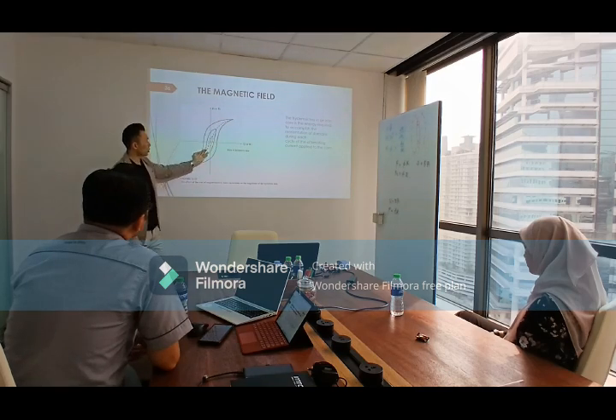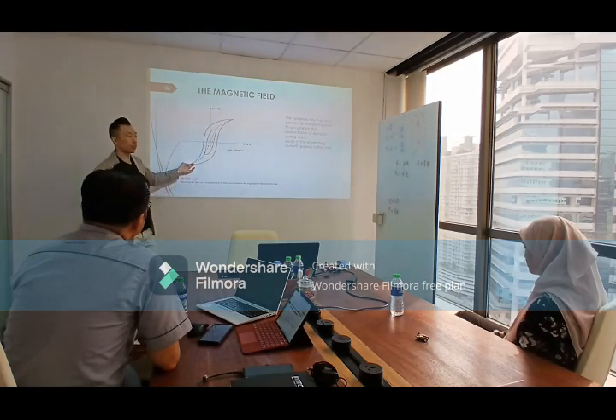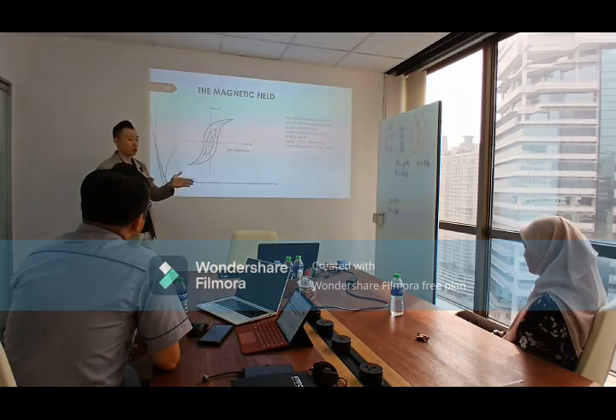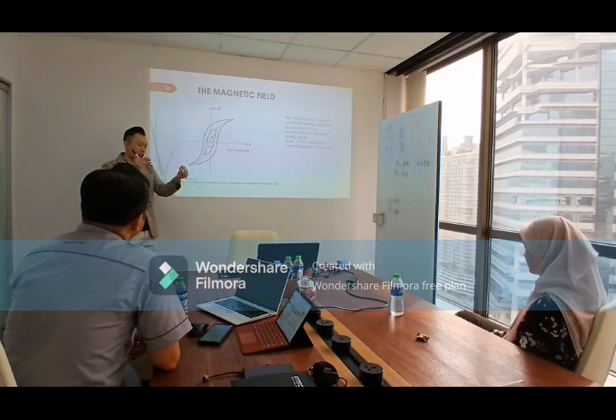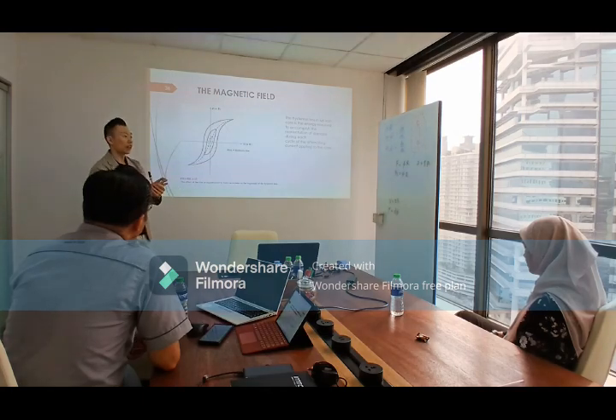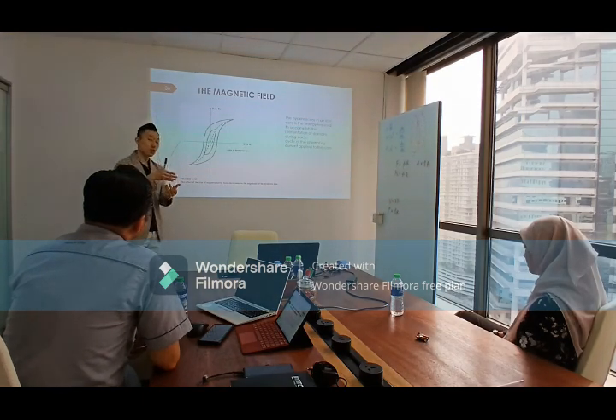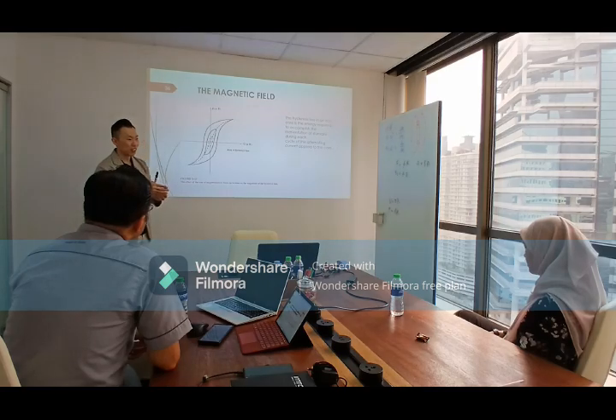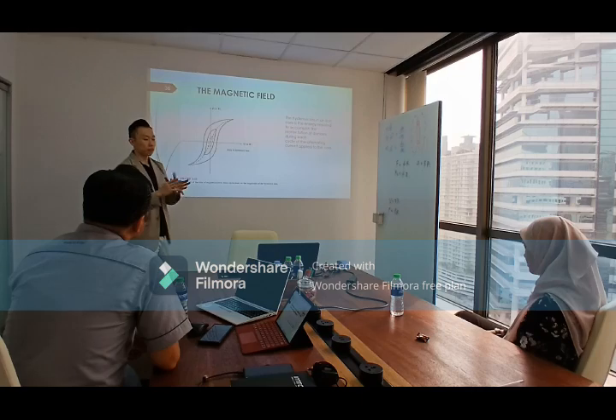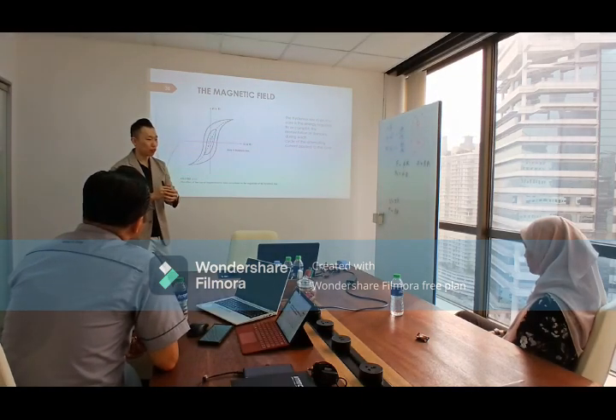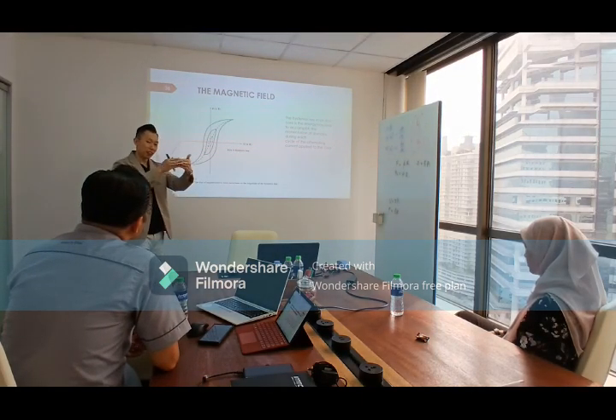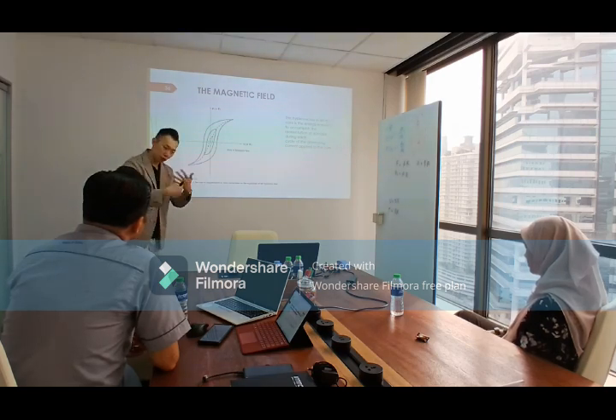So because of this hysteresis loop, you often hear that our stator cores are made of laminations of metals. The lamination wants to be as tight as possible, as thin as possible, each lamination. Why? If the lamination is thin, then less current can flow, or less field can flow. The behavior of magnetic field, fortunately, is somewhat similar to current. So if current cannot flow, magnetic field also most likely cannot flow. So if we make the plate thin, there's less area for the field to flow.